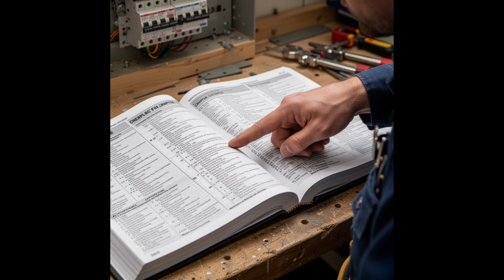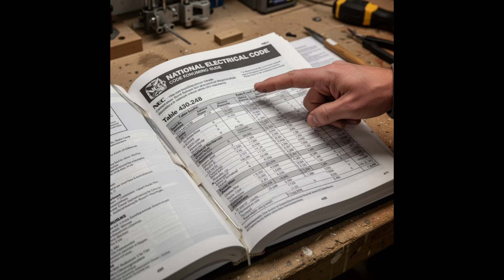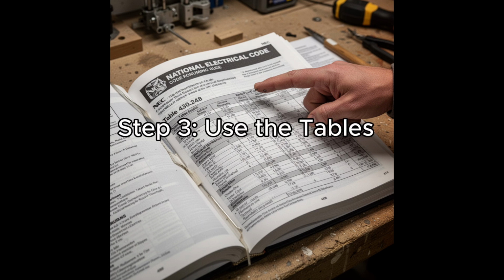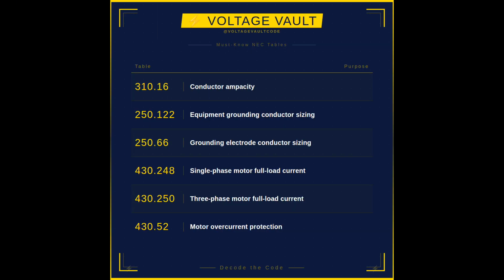Many NEC answers are found in tables. Learning where the most common tables are located can save you a lot of time. Tables 430.248 and 430.250 are easy to confuse. Table 430.248 applies to single-phase motors, while Table 430.250 covers 3-phase motors, which are much more common in commercial installations.